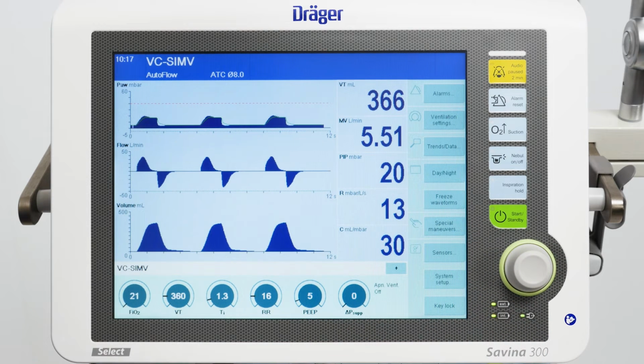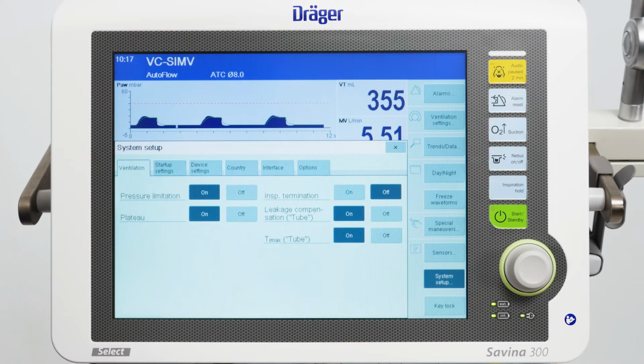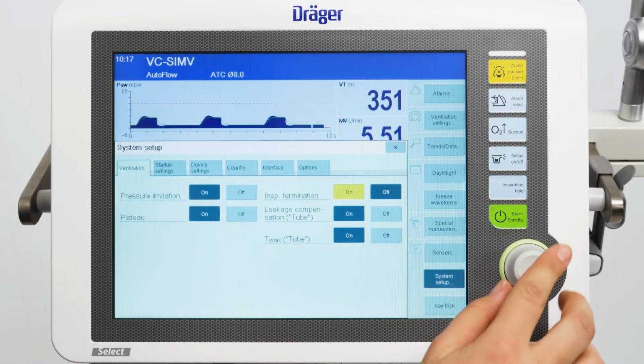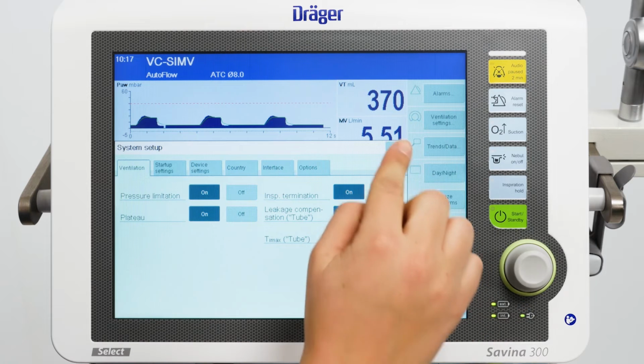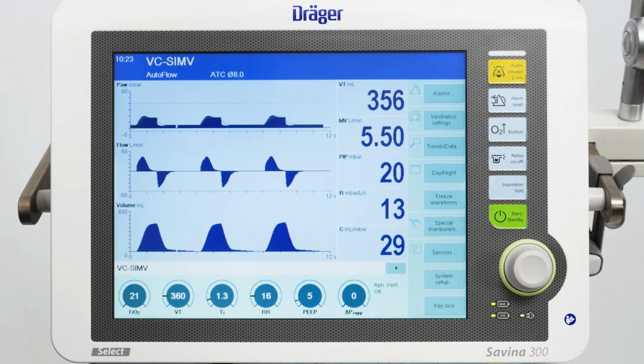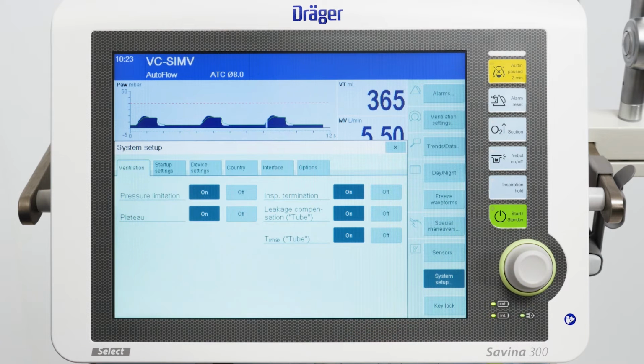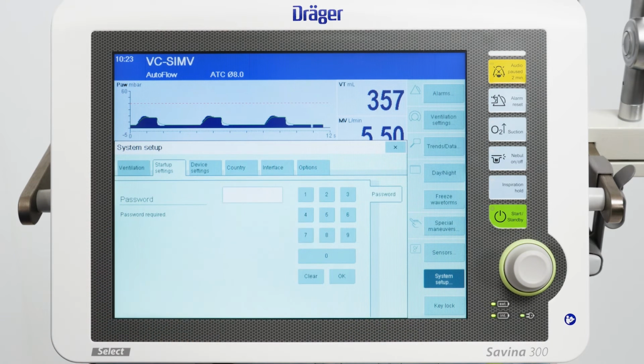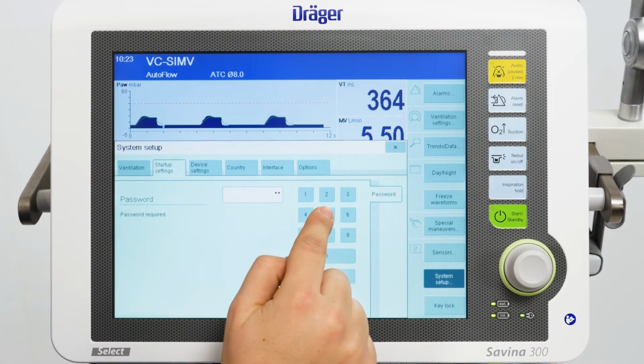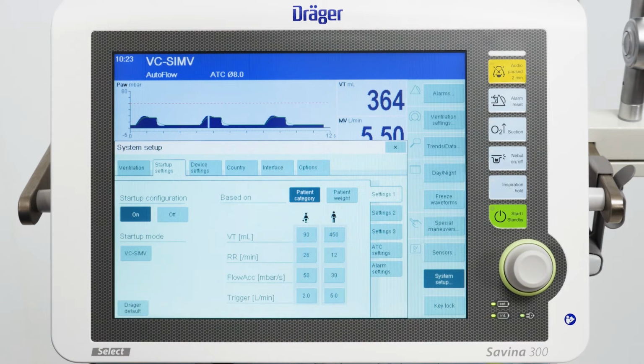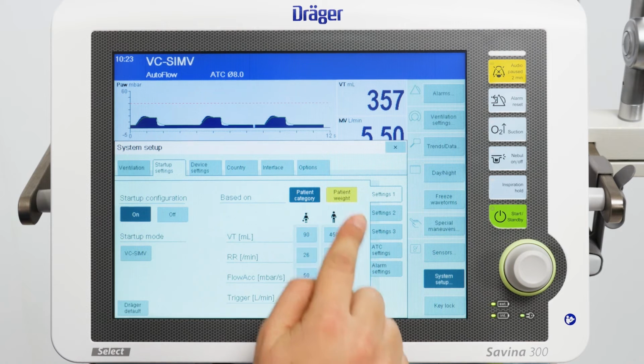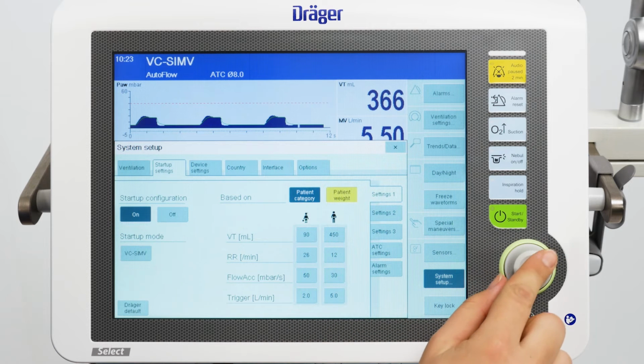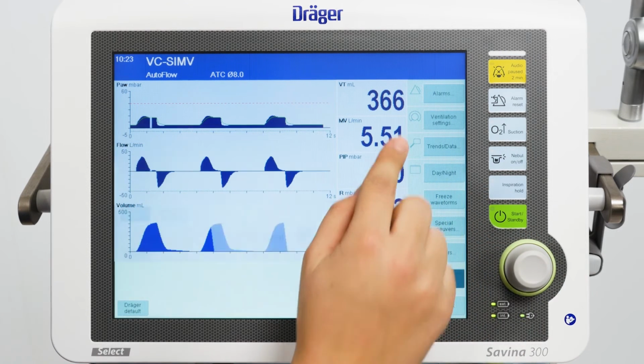On the Ventilation page, the ventilation functions Pressure Limitation, Inspiratory Pause Time Plateau, and Inspiratory Termination can be activated or deactivated. Touch the On or Off button and confirm with the rotary knob. To configure the startup settings, touch the button System Setup, then click Startup Settings. Type in the password and click OK. Now touch the tab Settings 1 and select either the patient category or the patient weight. Confirm with the rotary knob.